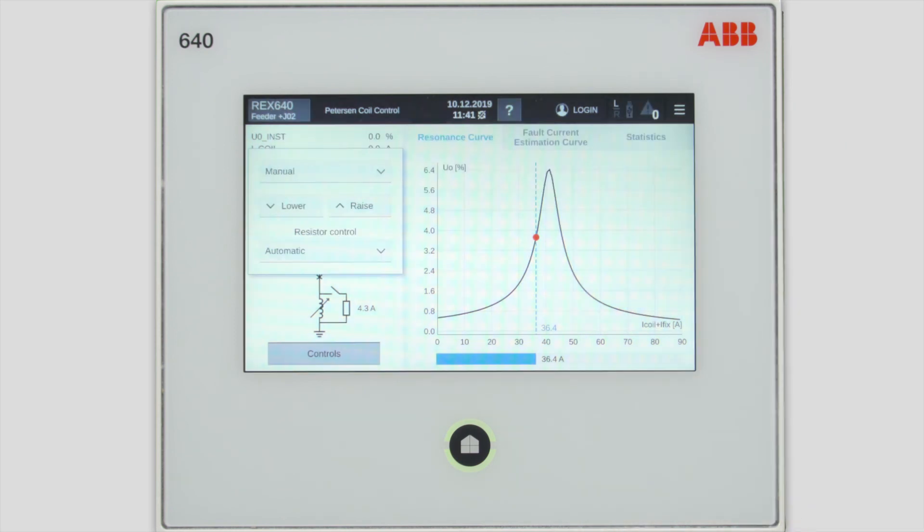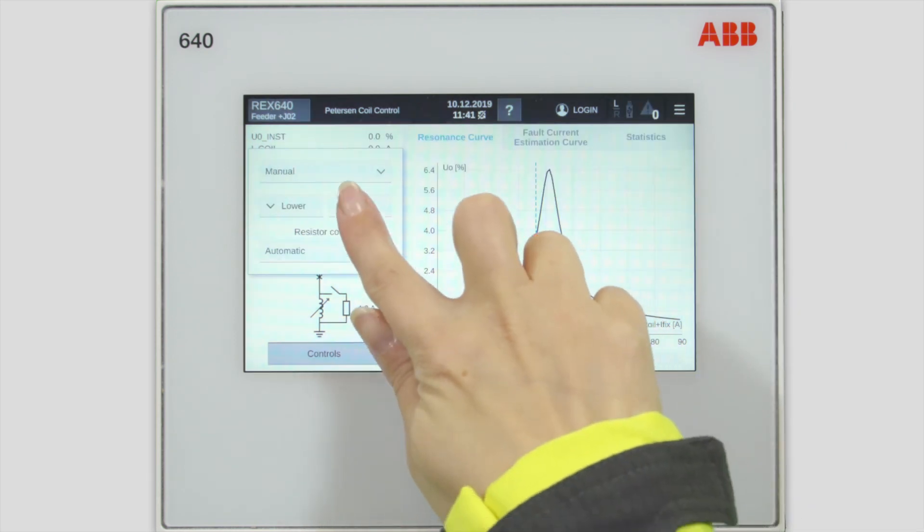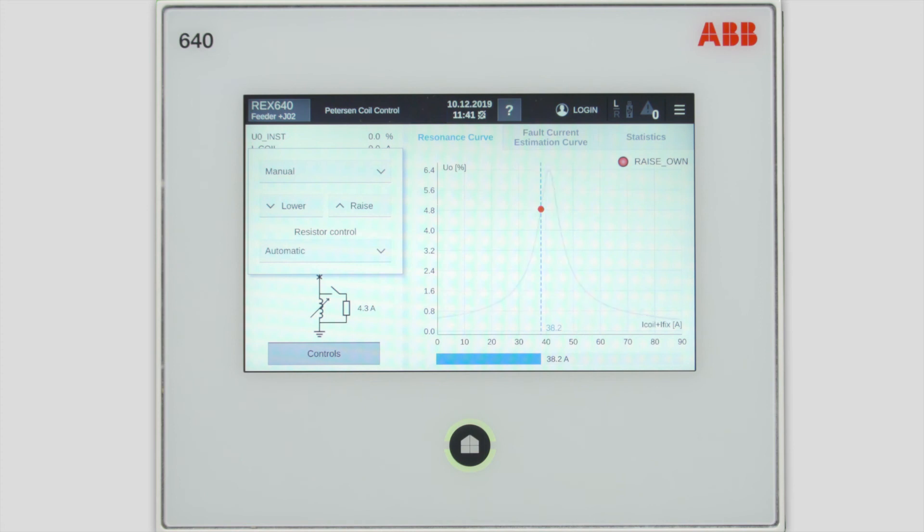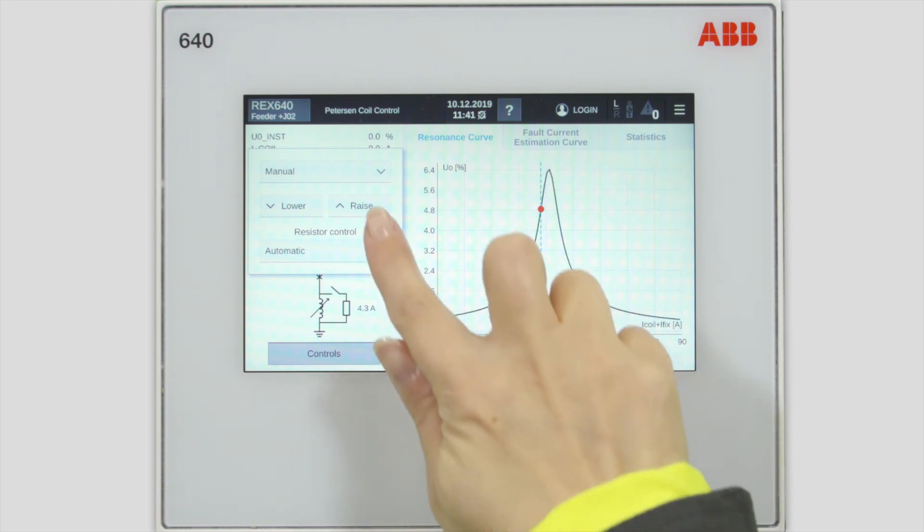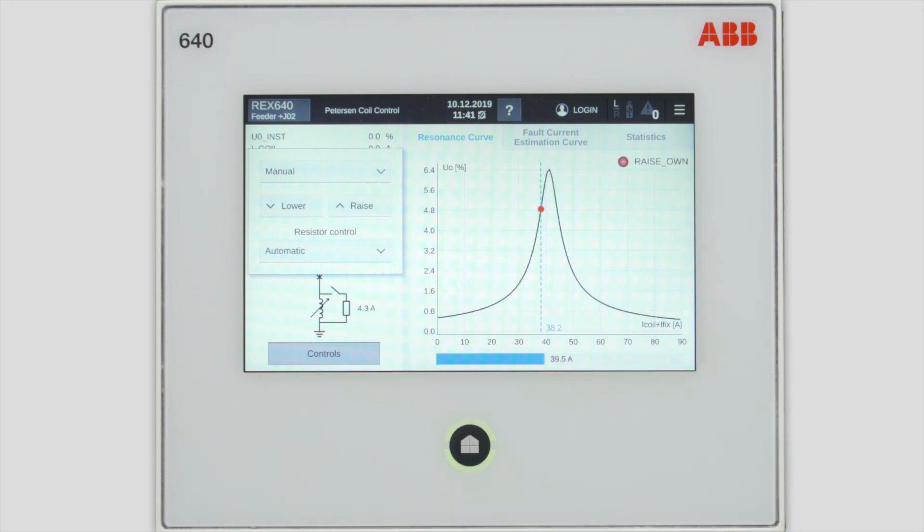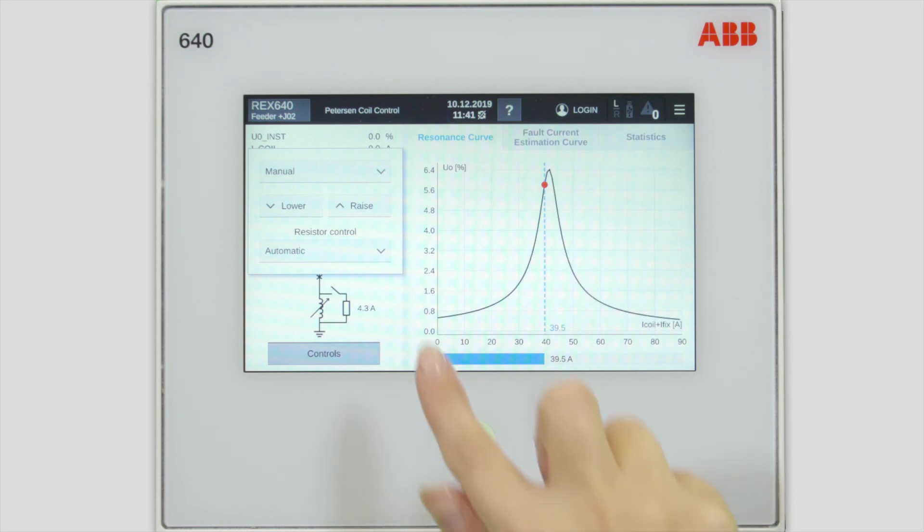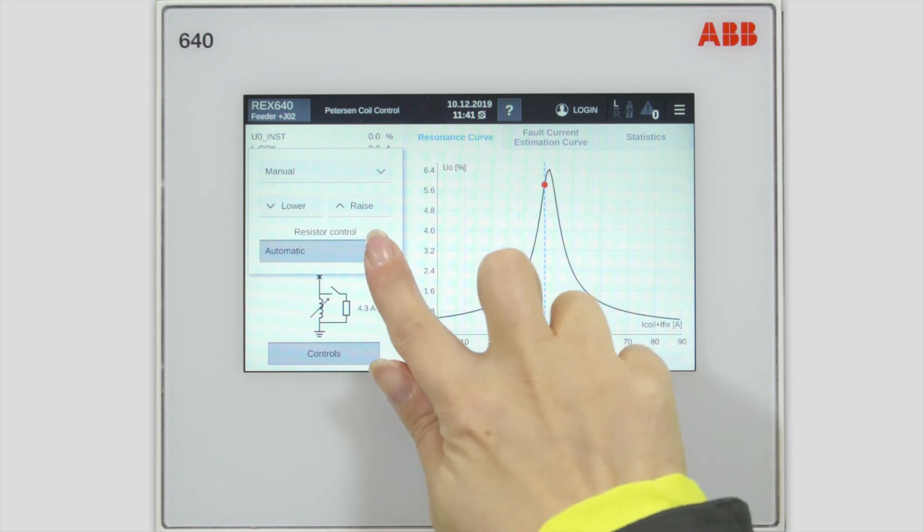Now you have lowered and raised buttons for the Petersen coil. In this case, you can determine that the coil is a bit under tuned compared to the resonance point. When you raise it up a bit, you can see from the resonance curve that the actual operational point will get closer to the resonance point.